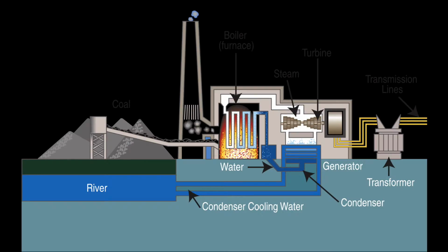In traditional electricity generation, coal is used as a fuel and chemical bonds are used as a source of potential energy. First, coal is brought in from a fuel supply area and is pulverized to form a fine powder. The pulverization of the coal increases its surface area and allows it to react more completely and release more energy in less time. The coal powder is then blown into the combustion area, furnace or boiler, and is suspended in the fire so the reaction can be as efficient as possible.